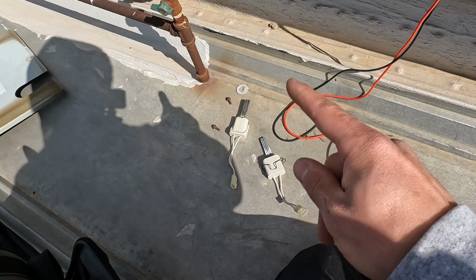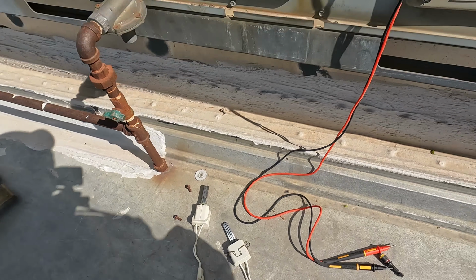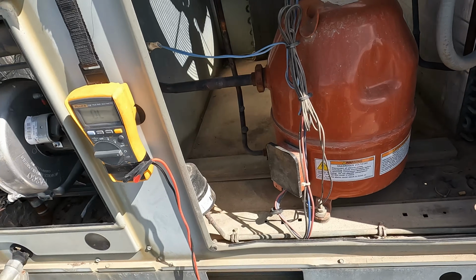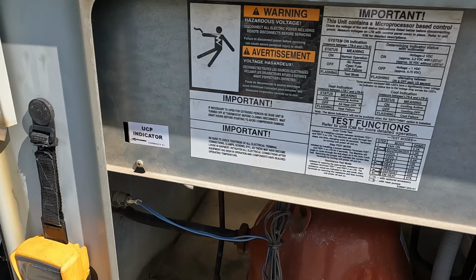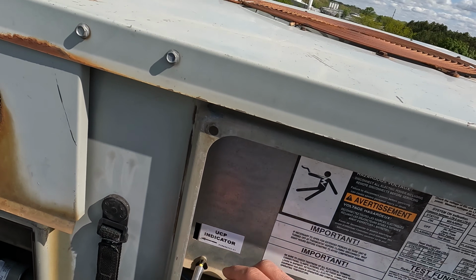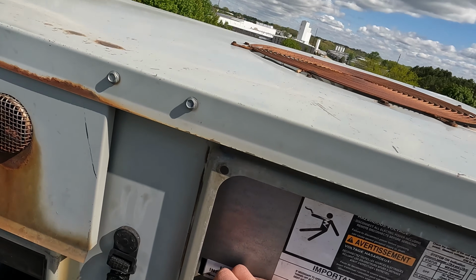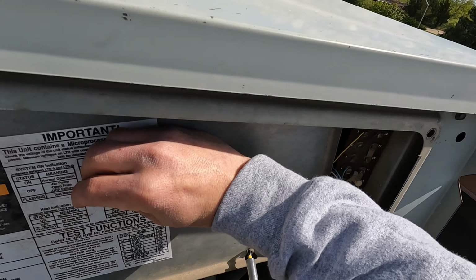Second, we can test flame rectification as well at the control board. So I'm going to try to find the flame signal port on there. He said that should be between 2 to 4 volts DC. Let's see if we can find that.